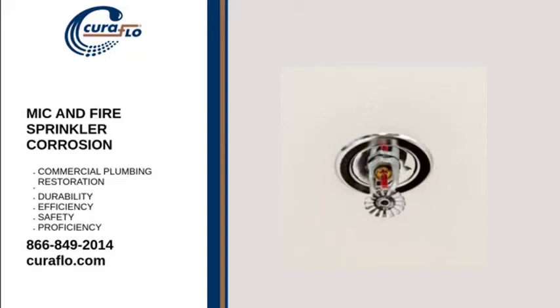MIC inside fire sprinkler systems can cause metallic system components to fail prematurely. Although steel piping is normally the first point of failure that is observed, MIC can be found in control valves, sprinkler orifice caps, supply tanks, and fittings. Localized corrosion due to MIC can be in the form of crevices, pitting, filiform, and cratering.